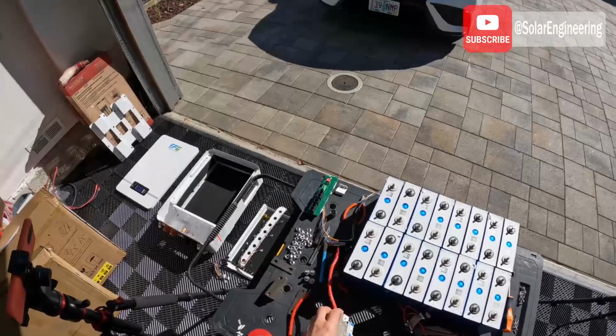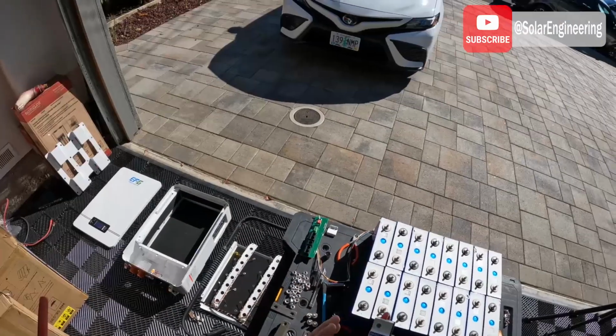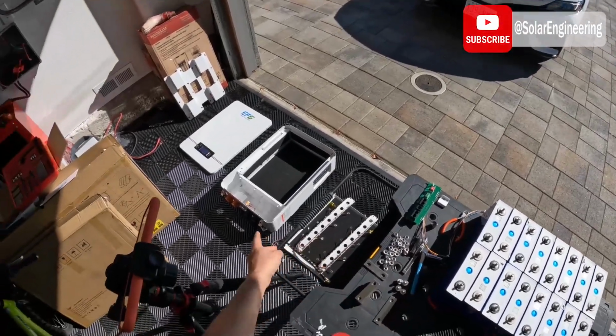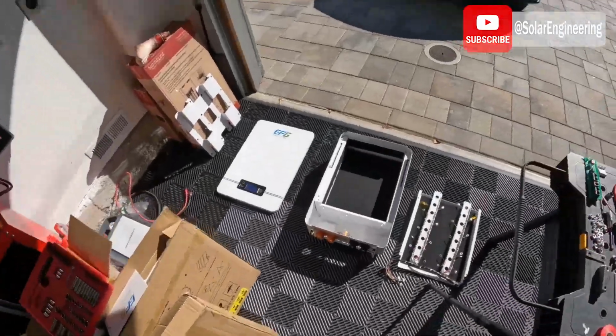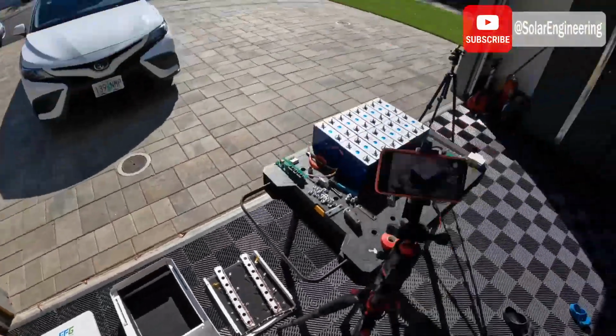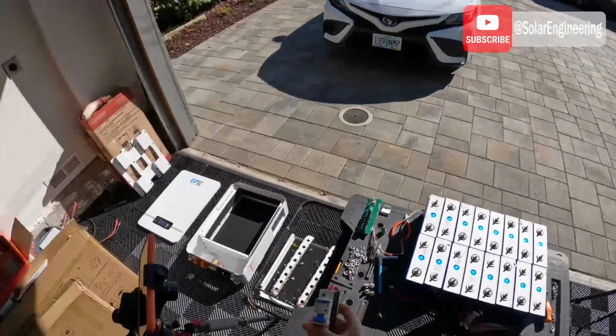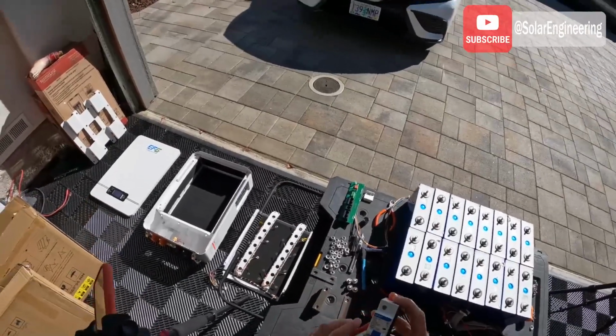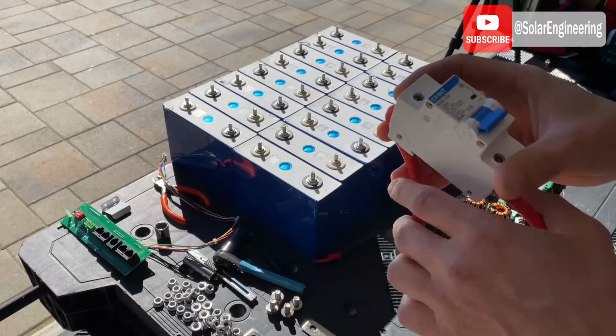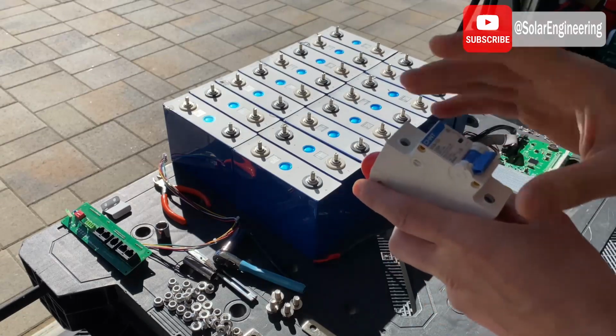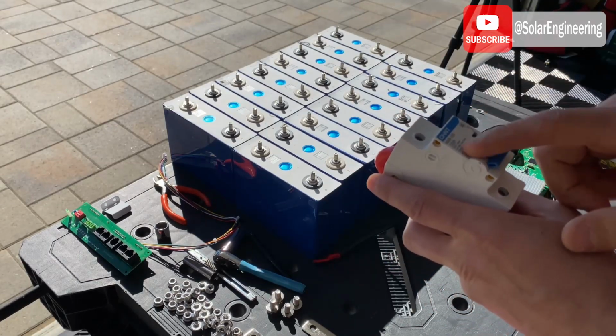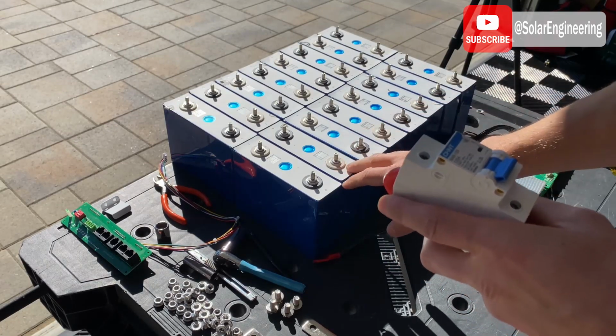For disconnect we have 2 options to disconnect this battery. First is a button on the box, this power button, and then we have these circuit breakers. This is a 125 amp circuit breaker, and what's interesting is this circuit breaker is rated for alternating current, so it's not rated for DC power.